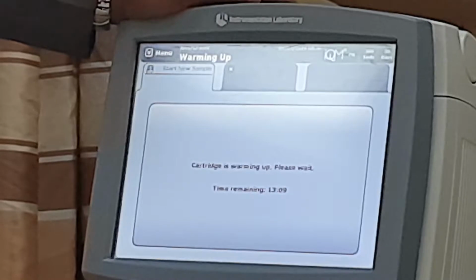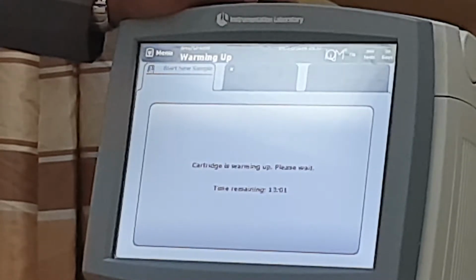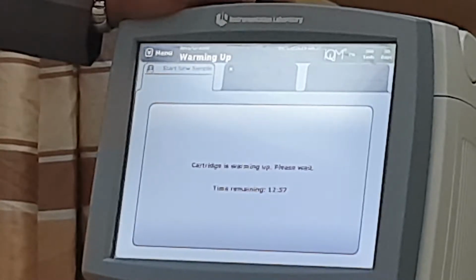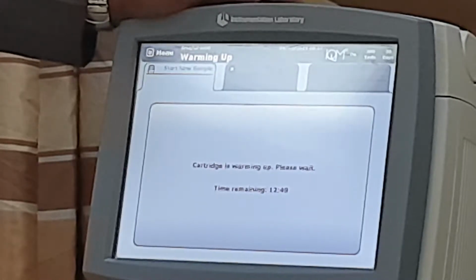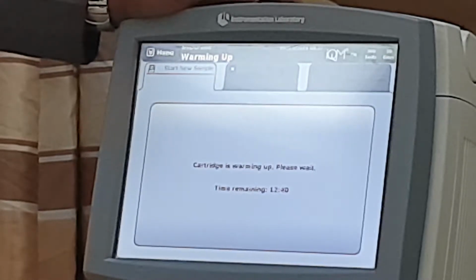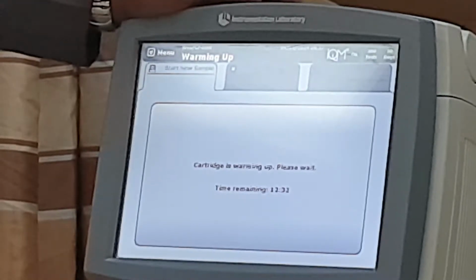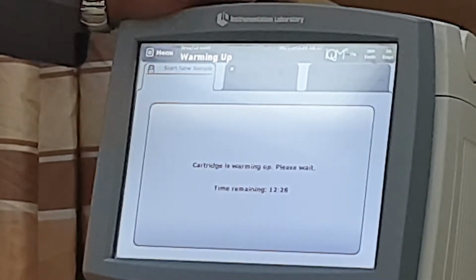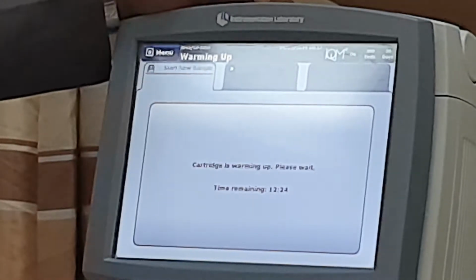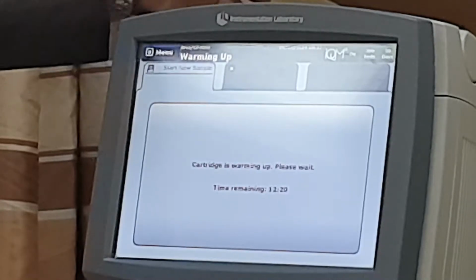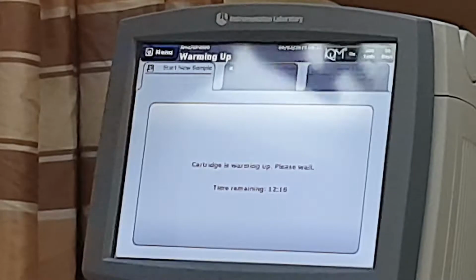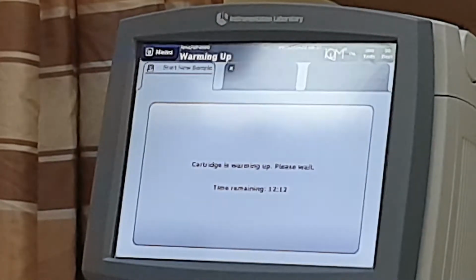The machine will also make documentation for you, or that software will make the documentation for you if you want to check. And the last thing, the machine will also make the delta chart for you. So we have 4 properties for that intelligent quality management software. Firstly, the machine will run 4 levels of control and detect if the control is out of range, correct it, make documentation, and finally make the delta chart. That means for the quality officer, it's very easy to get the files for the QC. Just insert the USB and get the copy. Everything will be there, from any error to the documentation, the revisioning, or the delta chart.